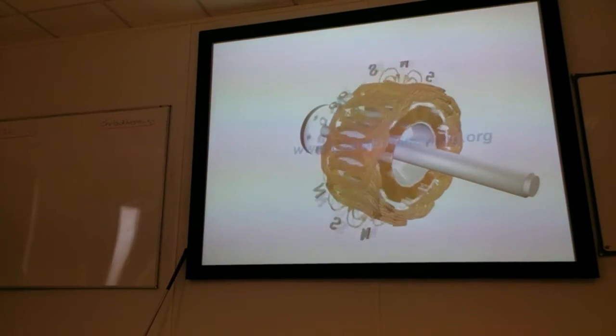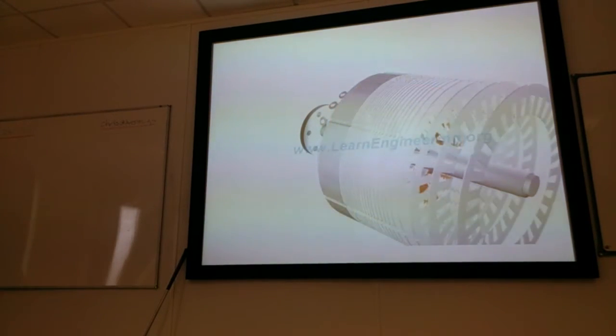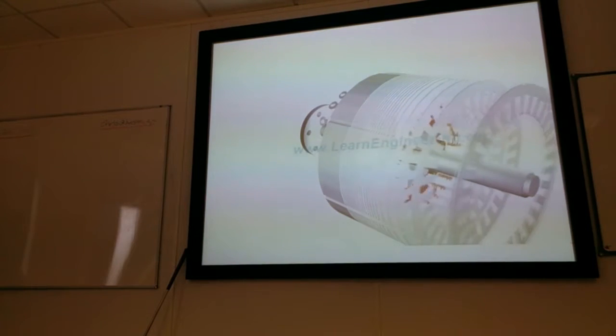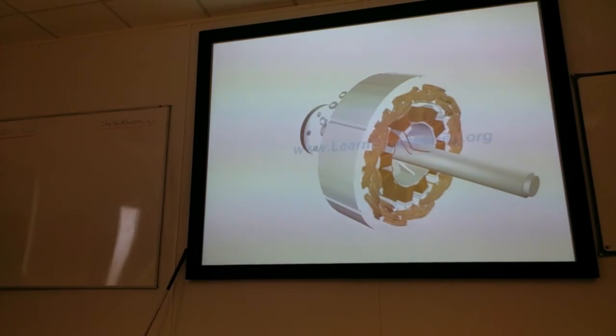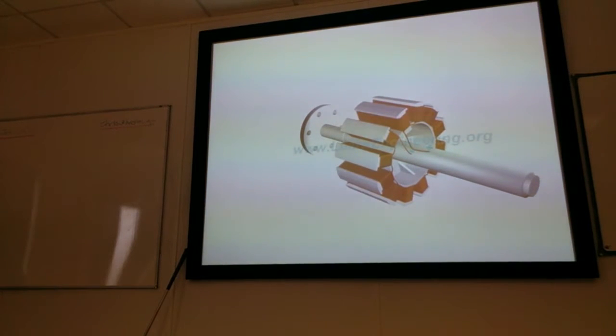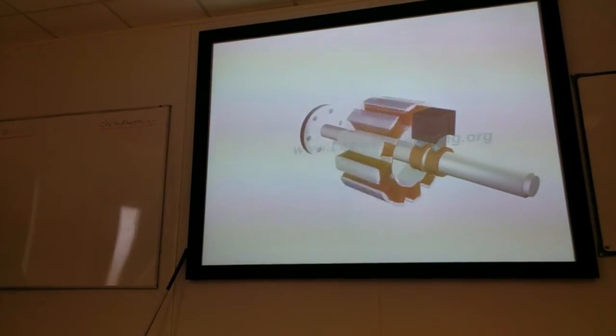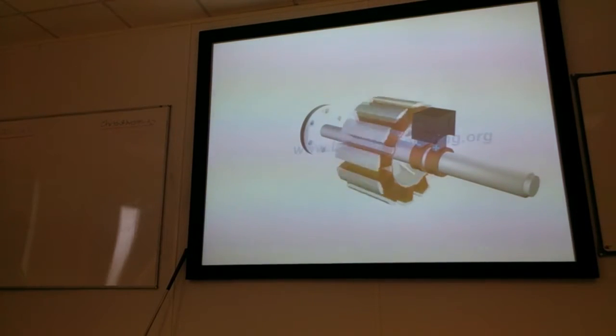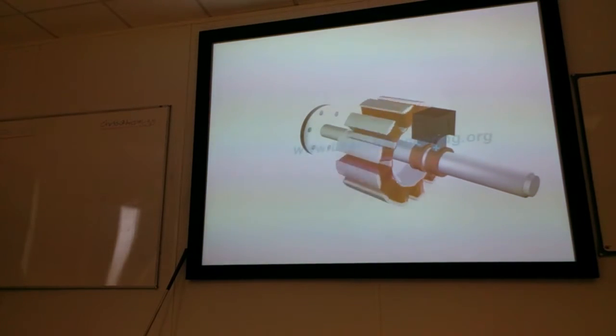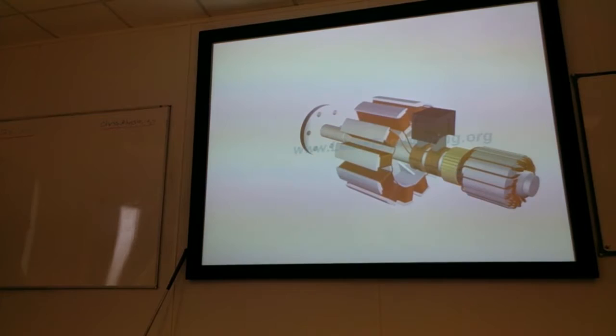A stator core is used to enhance magnetic flux transfer. DC current is supplied to rotor via a pair of slip rings. See those on the thing that's coming down the room now. DC current is supplied either from an external source or from a small DC generator, which is fitted on the same prime mover. Such alternators are called self-excited.